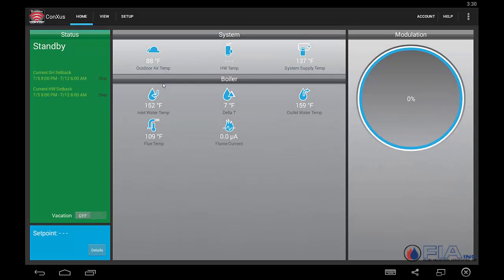Here we see the main screen of what's happening with our boiler at this moment in time. This boiler is currently in standby, not responding to a call or anything if nothing's been given to it at this time. We can look at all of our temperatures — outdoor temperature, system supply temperature, and our boiler temperatures. Over here, we'll see the modulation rate of the boiler. The boiler is currently in standby, so the modulation rate is zero.